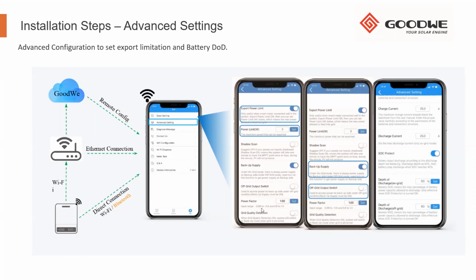You'll see we have the power factor adjust. This is normally just recommended to leave on 1. You only really adjust this should you have bad power factors on site, but that needs to be tested, and then you can adjust it to correct the power factor. But it's generally not recommended to adjust it on a domestic home.